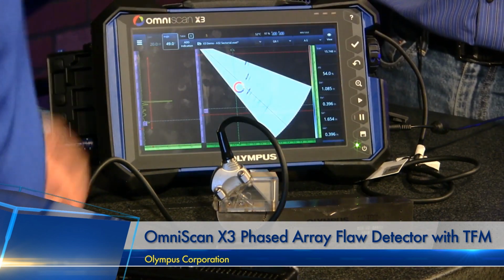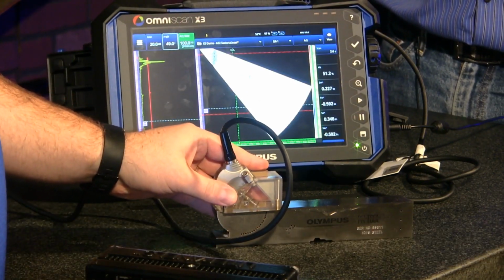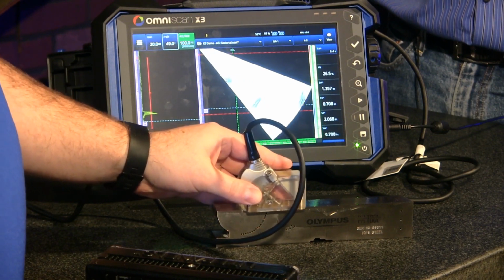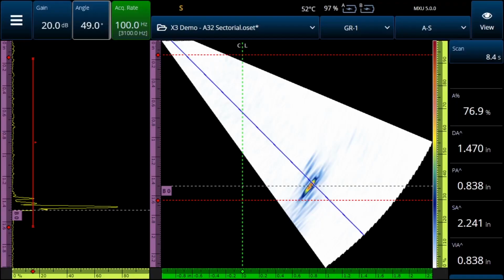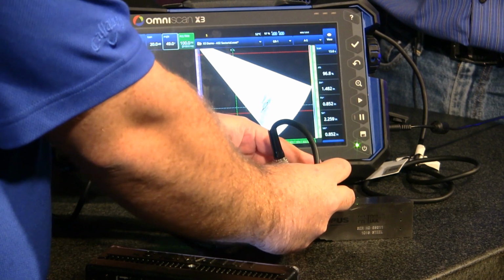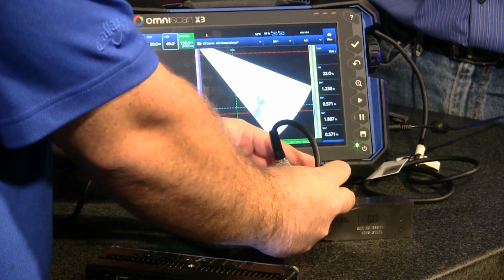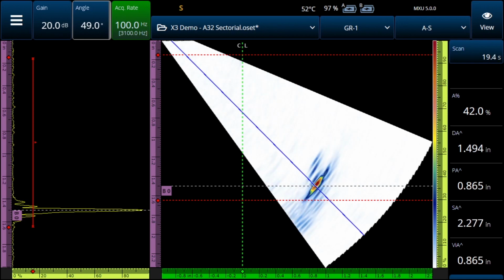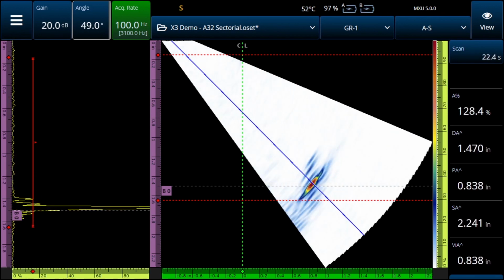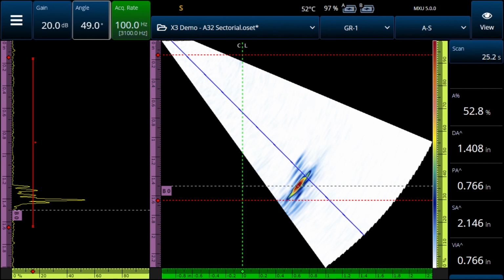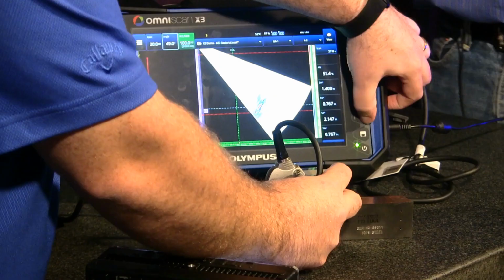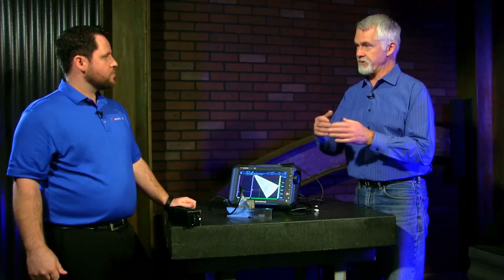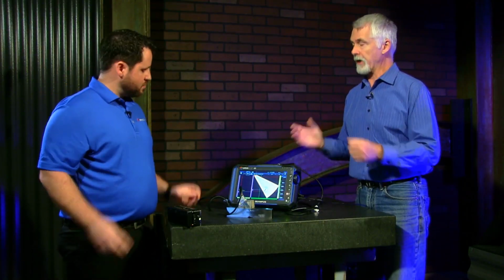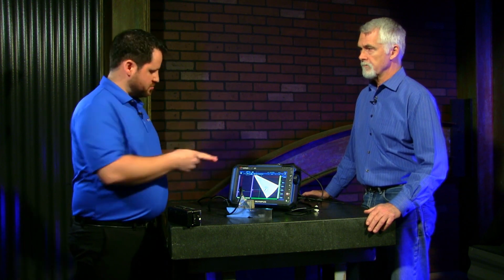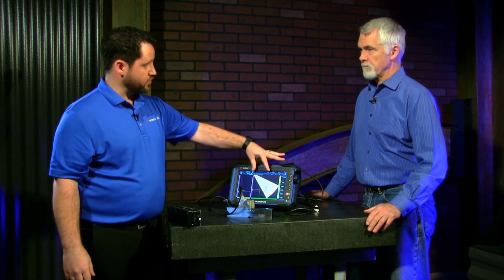And then if we go live with the system and we start scanning with the transducer, then typically the inspector would look for any indication that they may see, either scanning in and out on a part or perhaps scanning across a part. And then when they find a particular indication that they want to look for, they can skew the transducer, raster in and out on that indication, and perhaps stop when they've got a good view of it. So you're basically rotating the sensor to maximize the signal? Correct. Maximize the response, so that we can pause the instrument and then further evaluate with both what we see on the sectorial display and on the A-scan.